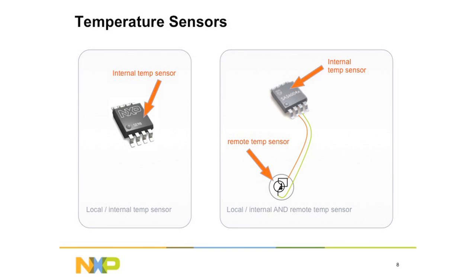The temperature data is also used internally by the temperature sensor to activate alarms if the temperature is too high or too low, and in some devices directly activate a cooling fan if a critical high temperature is reached before the normal high limit alarm is processed by the bus master. The alarm set points are programmed by the bus master over the same communications bus.